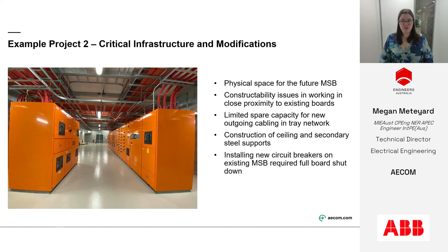And then installing new circuit breakers on the existing main switchboard actually required full shutdowns of the switchboard. So these were some challenges we faced in the main switchboard room. The next image is the main corridor that runs from the main switchboard room to the generator board.